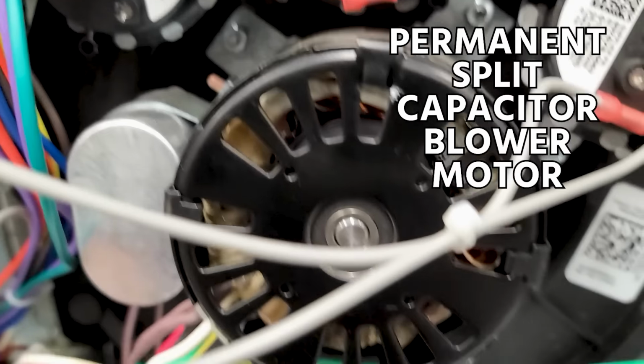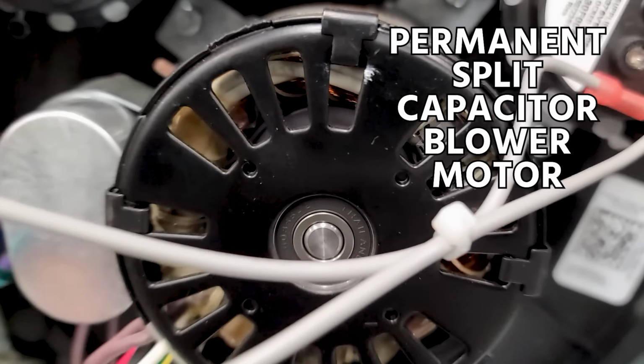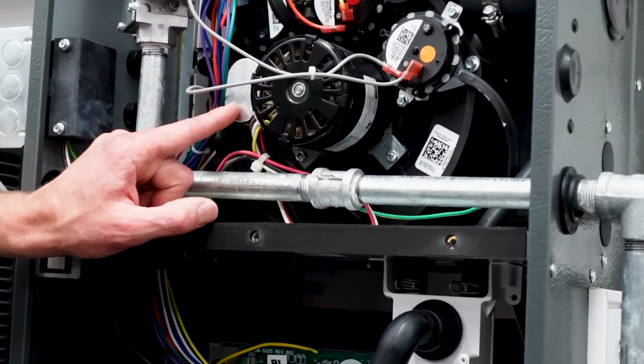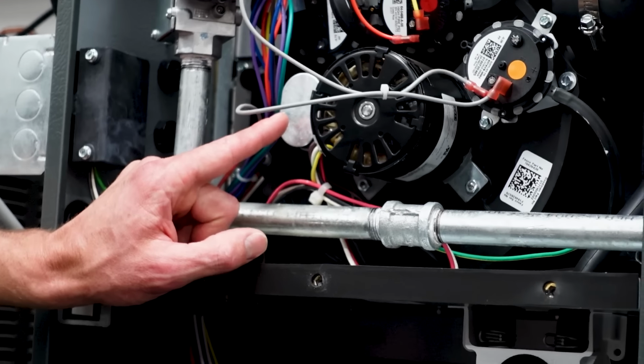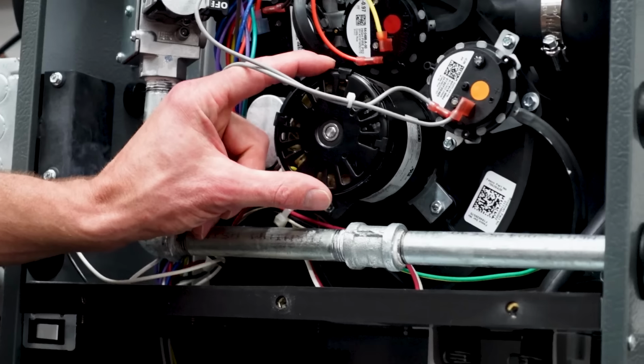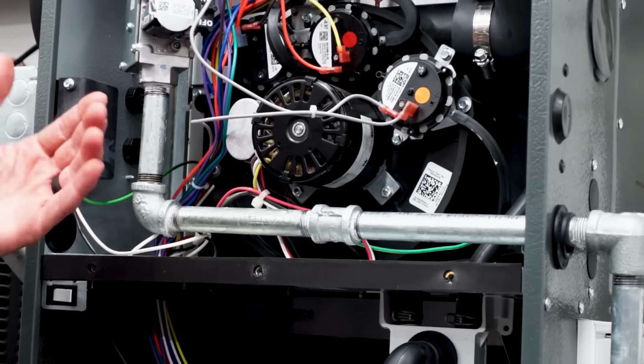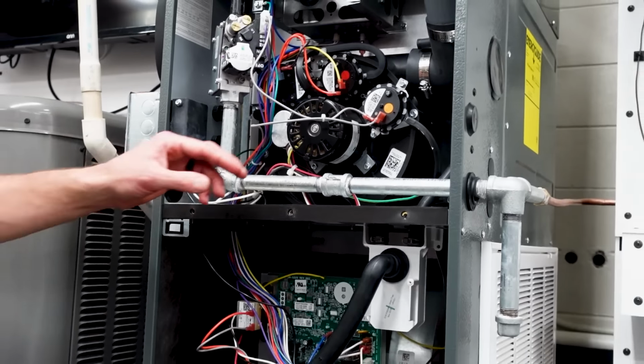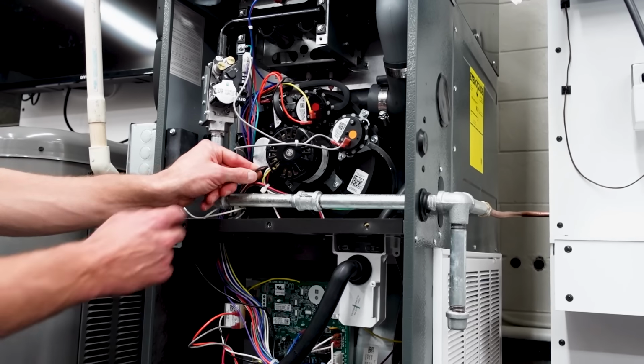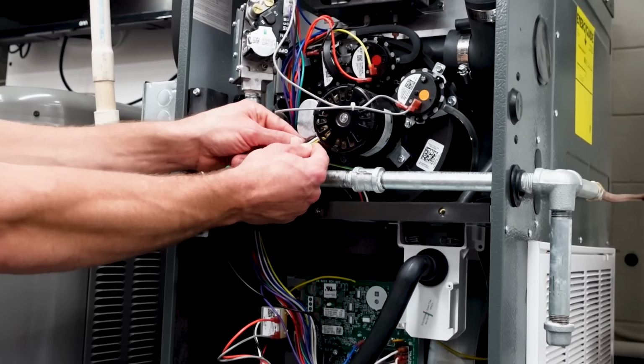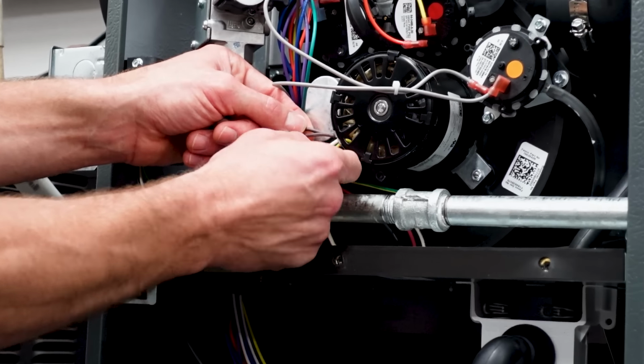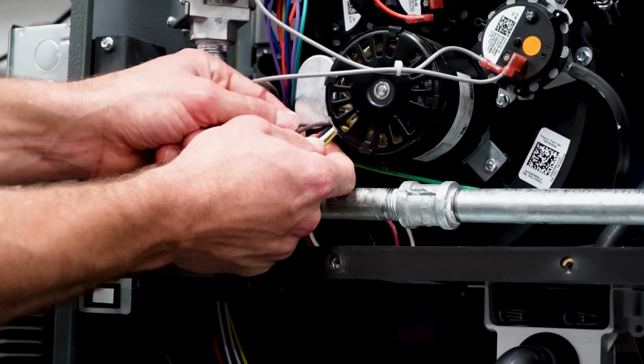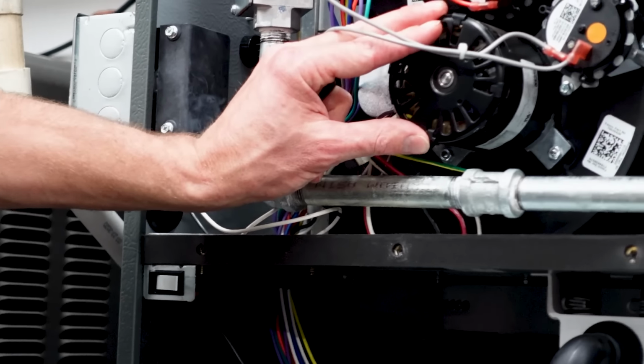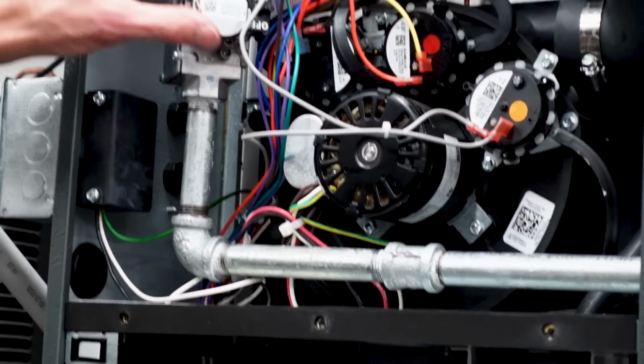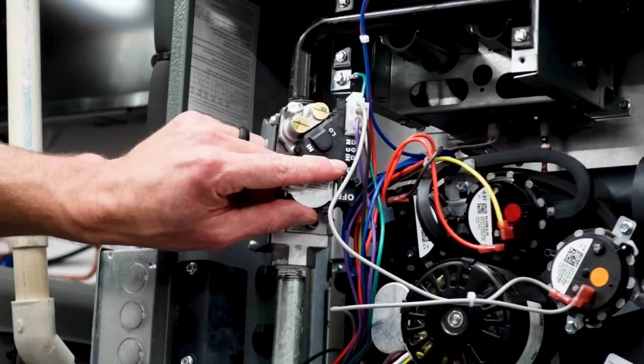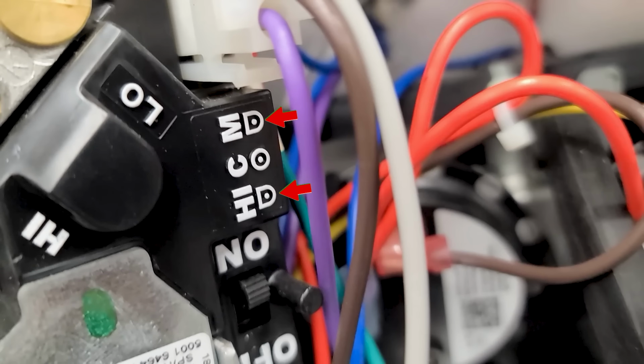This is the PSC inducer motor. That's a permanent split capacitor motor. So this capacitor, it's right there for you to see. That's what gives it the artificial phase in order for the motor to start up and to continue to run efficiently. And you see that there's more than just two wires and a ground. It actually has a multitude of wires right here, but basically this inducer motor should be running in 2 speeds because this gas valve is running in 2 speeds, and you have high, medium, and common.